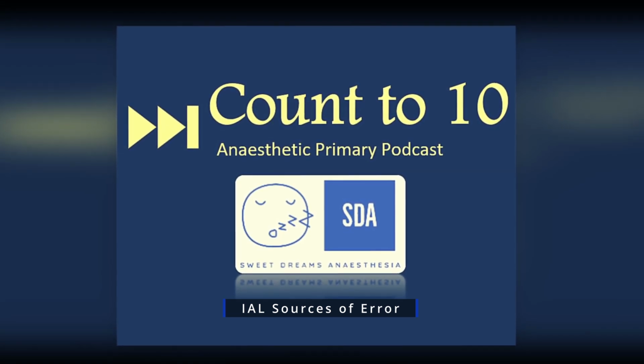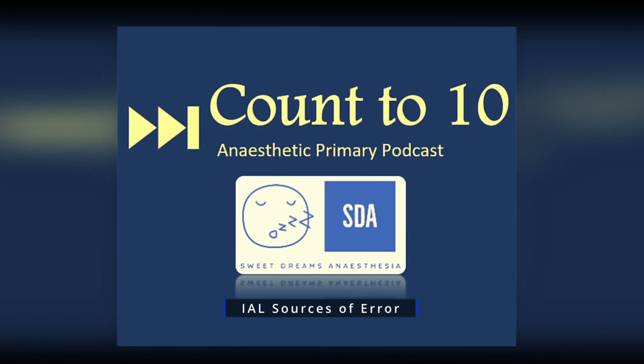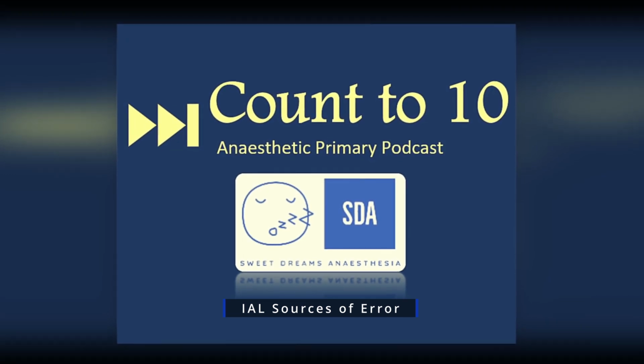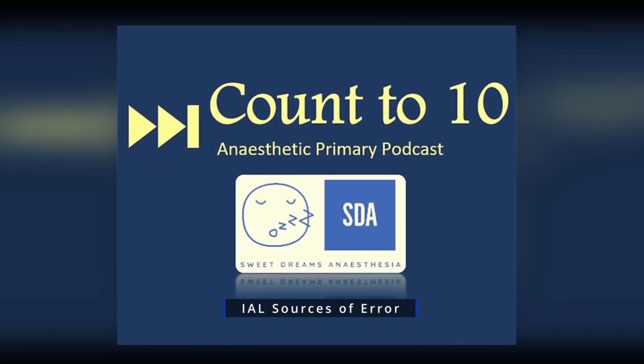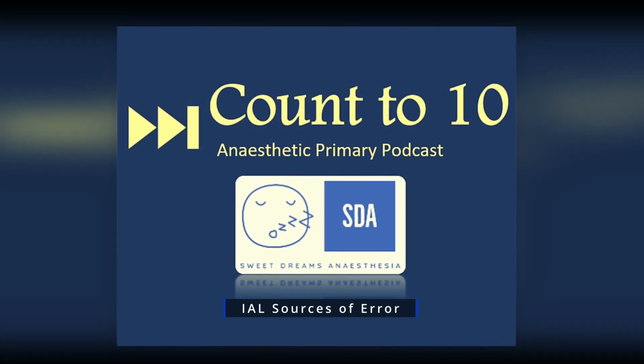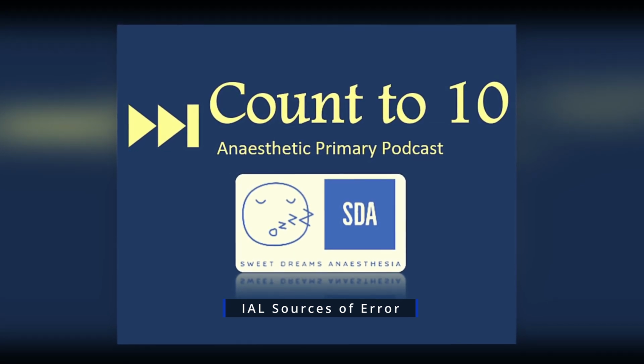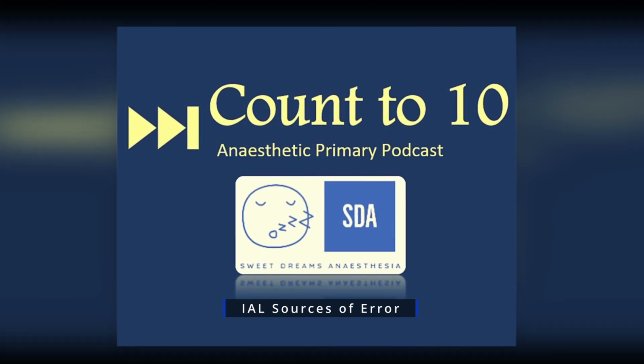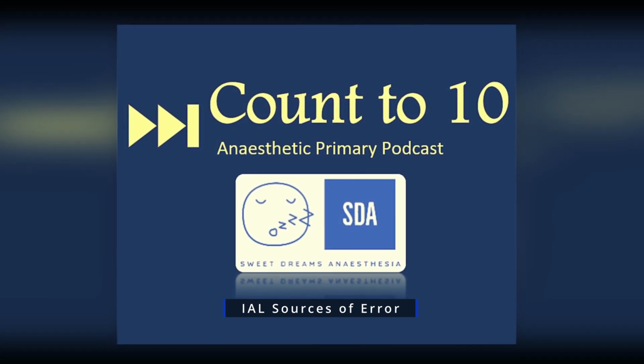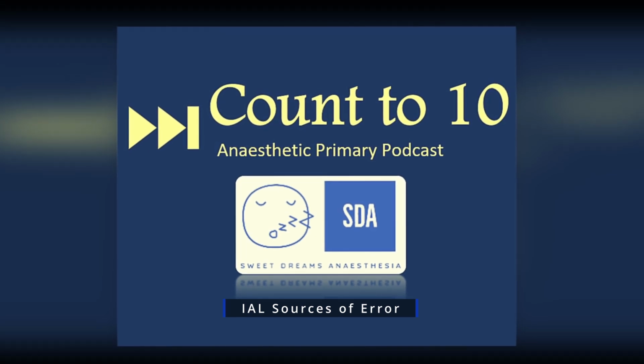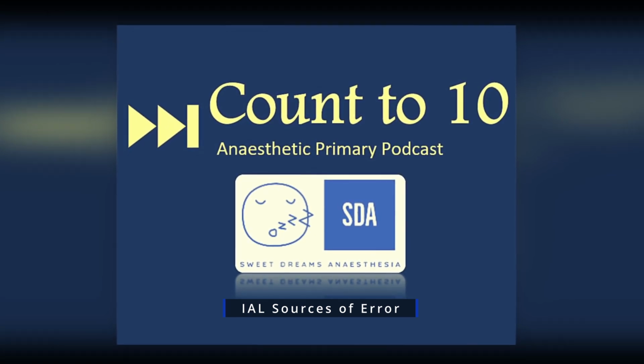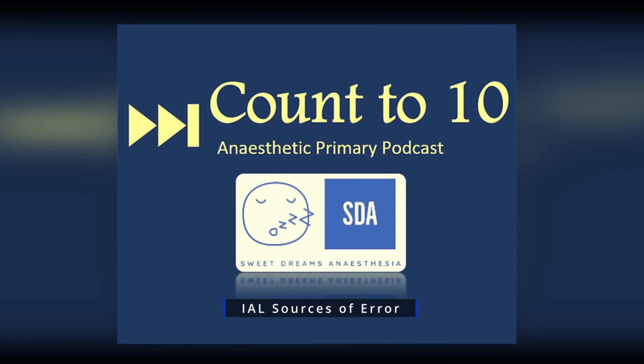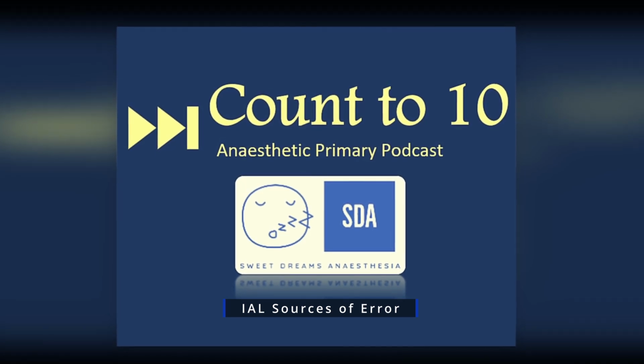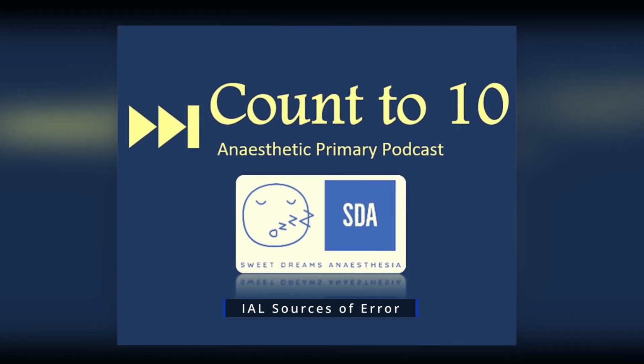Zeroing refers to having a reference standard to which the arterial line is measured to. The reference standard in this case is atmospheric pressure. So the way we perform this on an arterial line is we turn the arterial line off to patient and we open the chamber to air. This allows the transducer to measure atmospheric pressure, and this becomes a reference as 0. And when you have a range, you need to have an upper limit as well. The upper limit in this case is the pressurized normal saline bag.